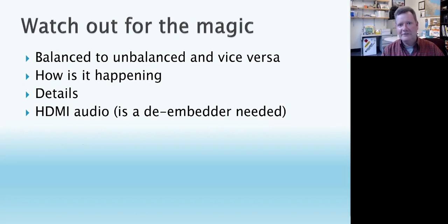This has come up several times. Often audio is left to, I'll be blunt, the new guys on the install team. If it's not specified how that's going to happen, I've seen people take the positive, the inverting, the non-inverting, and the ground, and tie them all together with little jumpers. They didn't know any better, not to pick on the young or inexperienced guys. So make sure that's specified in the design and done properly in staging, then during commissioning you can do a random check out in the field as a sample of what they're doing. But it needs to be specified, and a lot of that is what I call manufacturer specific.